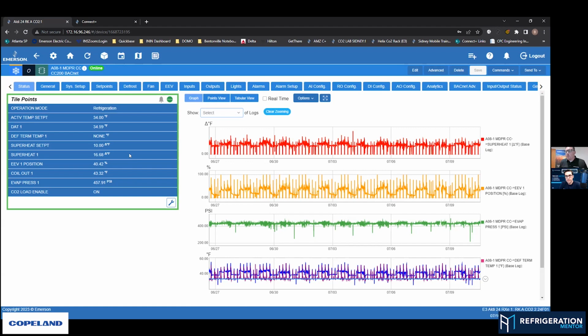The next step is bringing them online with the supervisor controller in E3. Are the files all loaded correctly? Is our communication port set correctly in the E3? And we've got to address the device too, because it needs to know who to talk to as far as the E3 is concerned. If you've got 5 cases and they're all addressed as 1, trying to communicate to 5 ones isn't going to work. So making sure our addressing is correct in the controllers, both at the case and at the E3, to ensure peer-to-peer communication.